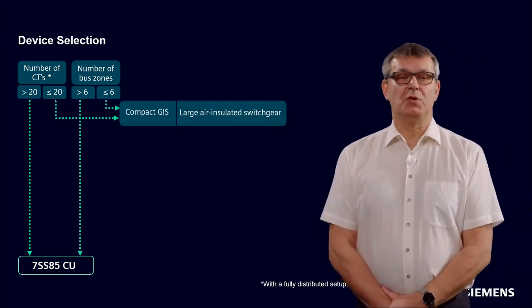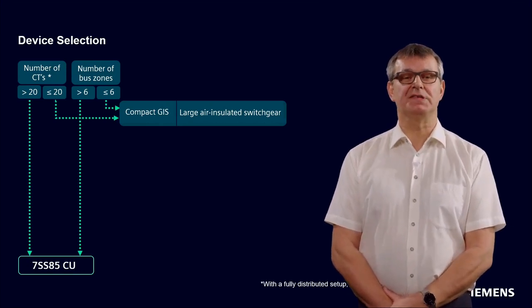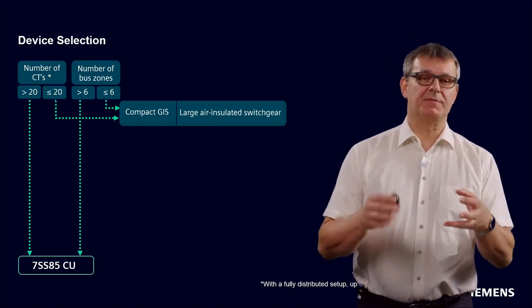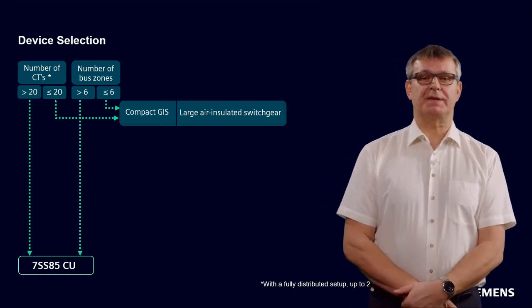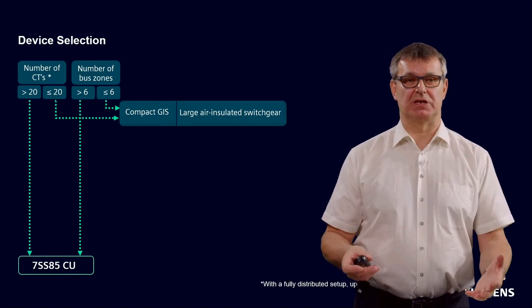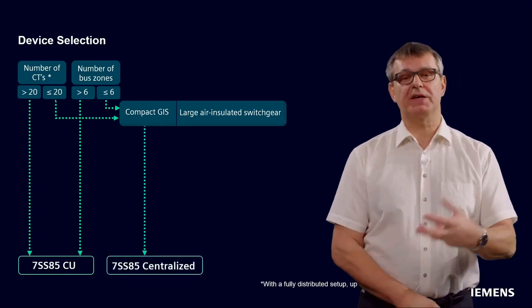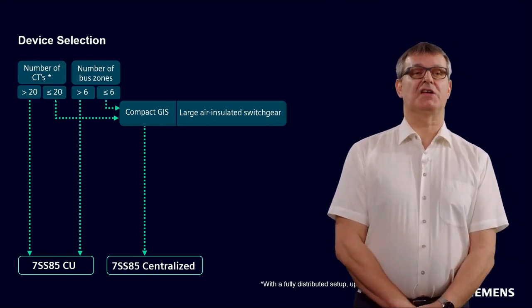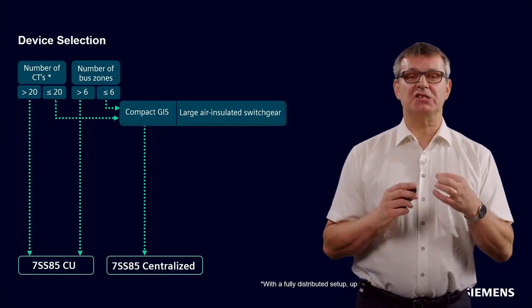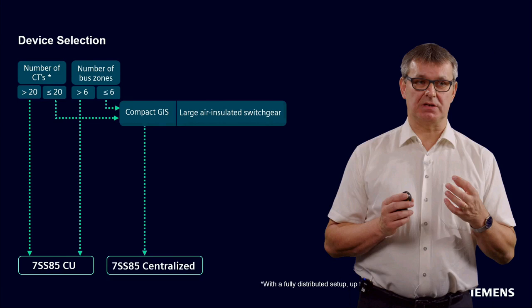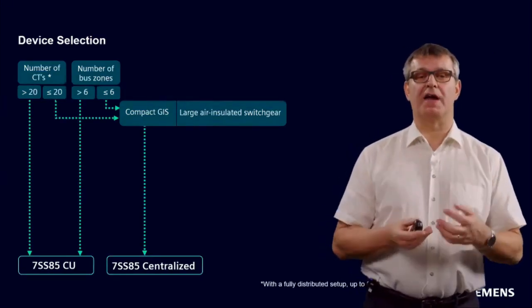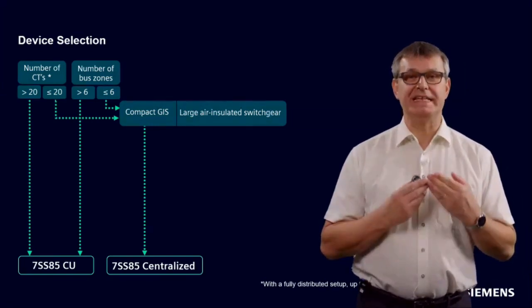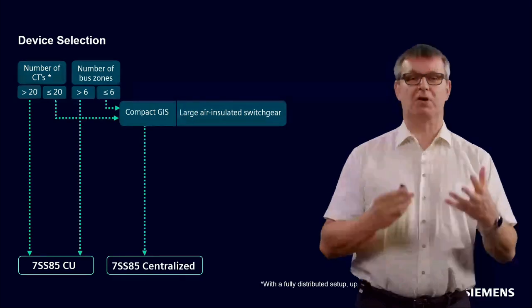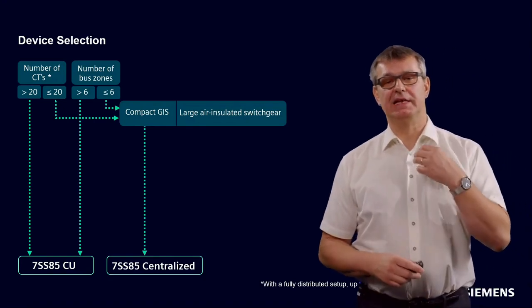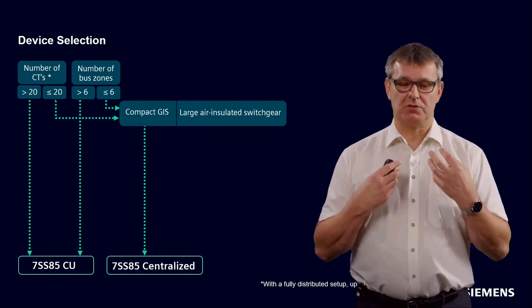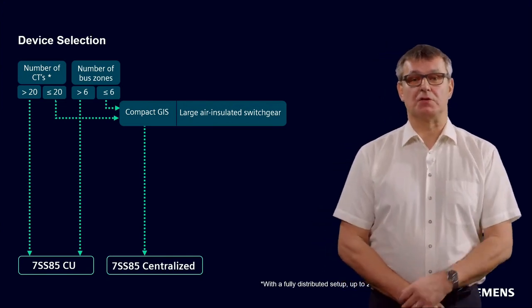Then the next questions. If you are below 20 CTs and below 6 zones, then you have to ask: is my substation a compact, small, gas-insulated substation, or do I have a large air-insulated switchgear? If we have a compact GIS, okay, we can deal with a centralized busbar protection approach. If it's a large air-insulated switchgear, as I have already explained, a very big substation, you need a lot of cable, a long wiring distance between the primary CTs and your device, which means a high burden on the primary CT. Such a high burden could lead to an earlier CT saturation, which would risk a wrong tripping in case of an external fault. This is very important.